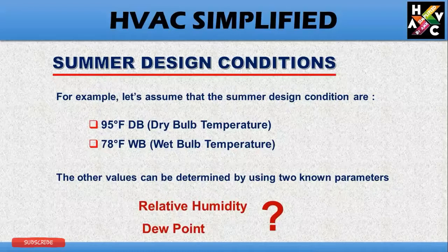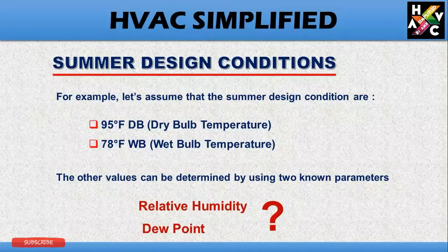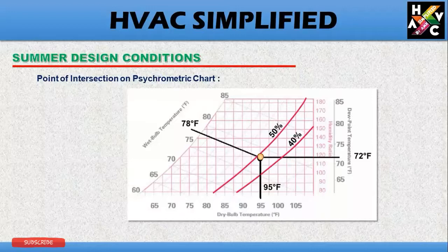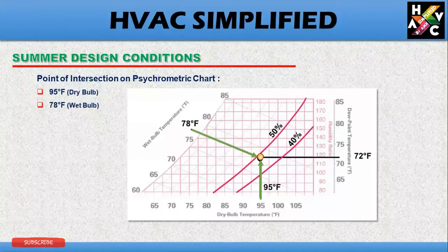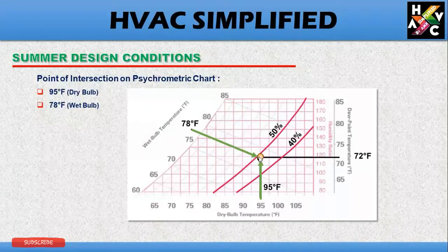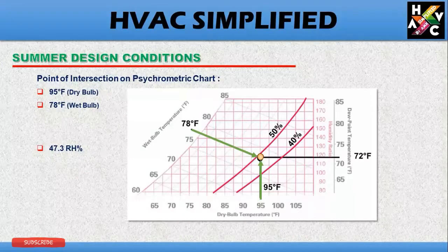Let us find the relative humidity and the dew point temperature on the psychrometric chart using 95°F as the dry-bulb and 78°F as the wet-bulb. The dry-bulb temperature at 95°F intersects with the wet-bulb temperature at 78 degrees Fahrenheit — this is your point of intersection. At this point of intersection, your relative humidity is approximately 50%, and to be precise, 47.3%.